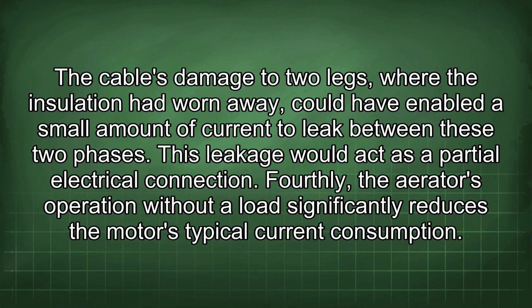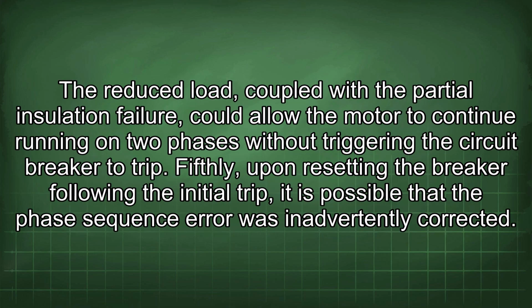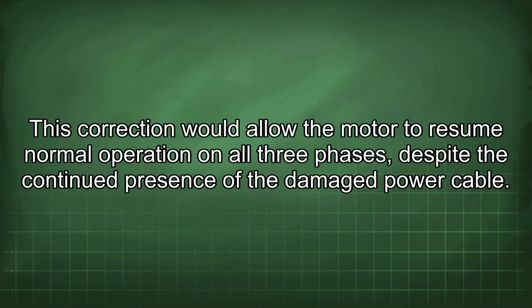Fourthly, the aerator's operation without a load significantly reduces the motor's typical current consumption. The reduced load, coupled with the partial insulation failure, could allow the motor to continue running on 2 phases without triggering the circuit breaker to trip. Fifthly, upon resetting the breaker following the initial trip, it is possible that the phase sequence error was inadvertently corrected.